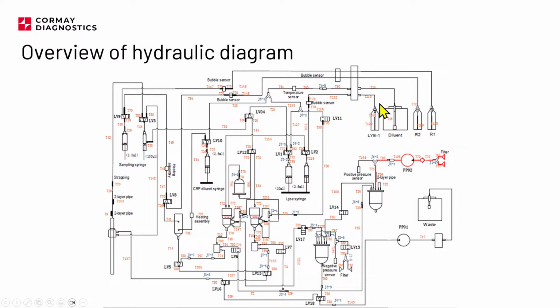As you can see, the lye circuit for hematology is very simple. We have the bottle, we are going in, and this is the reagent or, sorry, bubble sensor. So this is the back panel, bubble sensor, one valve, three-way syringe, and then we are going to the WBC chamber. And that's it. This is the whole lye circuit. Very simple. Diluent, temperature sensor, and also there is a diluent detector.